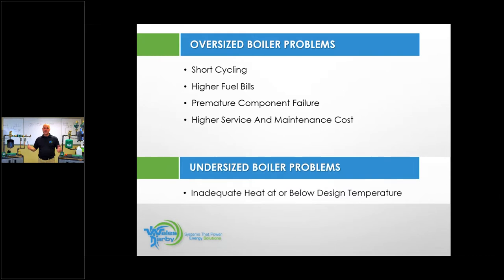Undersizing a boiler, it's just not going to heat the home properly, depending on what the outdoor temperature is. Usually as you get colder outside, you won't have enough BTU to heat the home. That's what undersizing will do. So, just why we got this on here, I always talk a little bit about condensing modulating boilers. You never really want to oversize a condensing modulating boiler. I know they modulate. I know they have turndown rates. Jim will talk a lot about this next week, but we want to make sure that we size that boiler properly. Always look at your smallest heat circuit in the home, and then look at your boiler size and say, when this thing is turned all the way down, how close am I to my smallest heat circuit? And figure out if that boiler is the right one for that job.